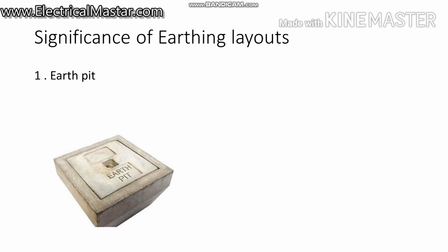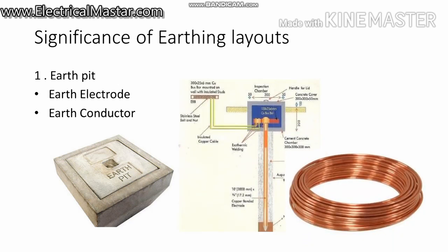So first one is the earth pit. We know the earth pit is like a house of the earthing connections. Inside the earth pit there will be an earth electrode and an earth conductor. An earth electrode is nothing but an earth rod. You can see this picture. This is the earth rod, also called an earth electrode. And the earth conductor is the earthing cable. Both the earth rod and the earth conductor are connected inside the earth pit.